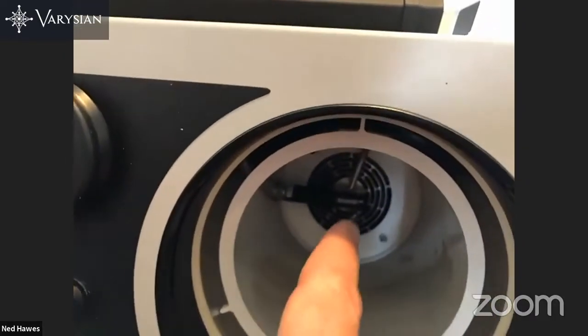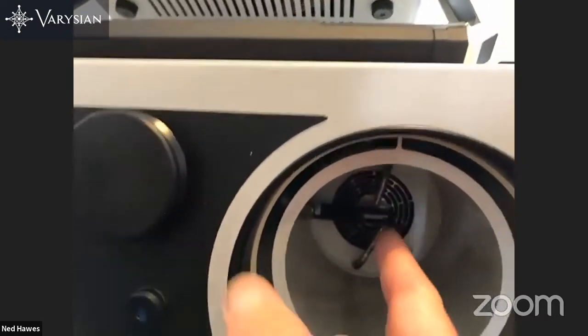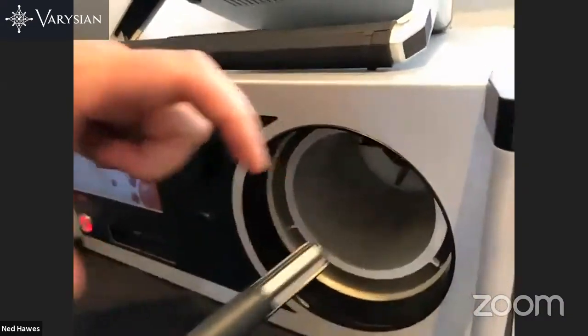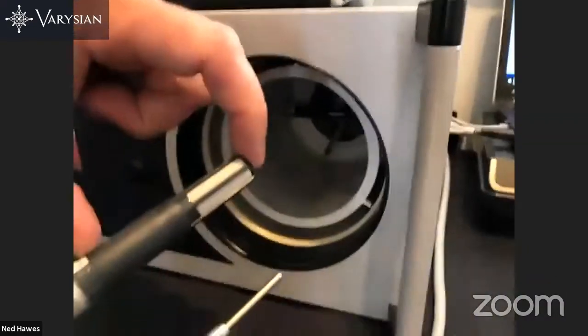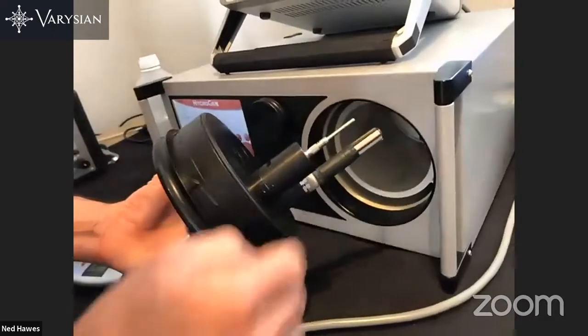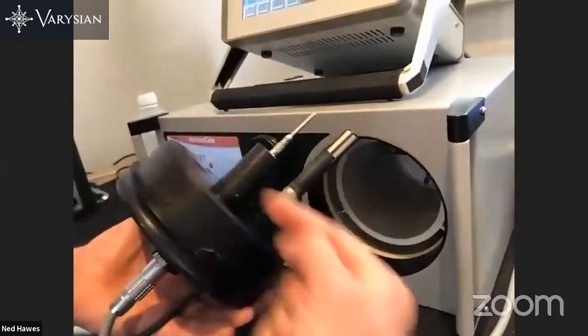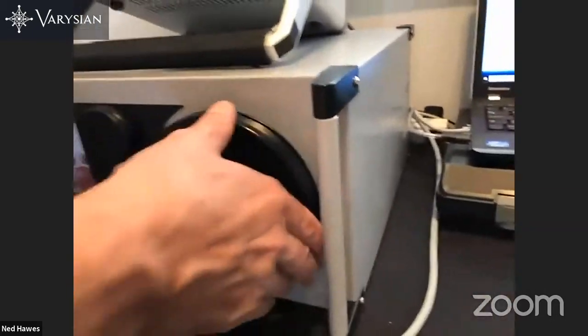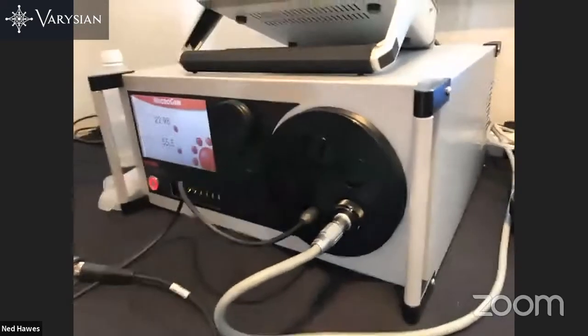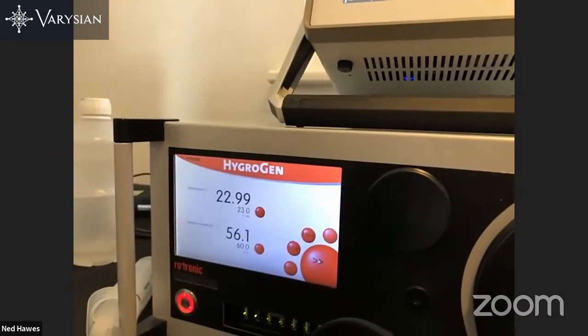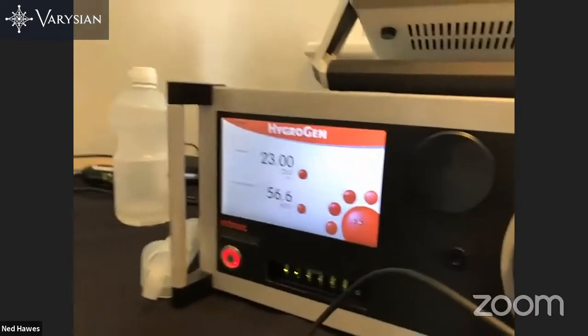Within the HygroGen itself, the actual condition is controlled by the RH point, which is not a particularly accurate device, but it's measured by the RP2 head, which is. So we compare what the instrument under test is reading against this. If I put this back in, the airflow comes from around the chamber and goes across the mirror surface. Now it's gone unstable because I opened the door, and it will restabilize itself.